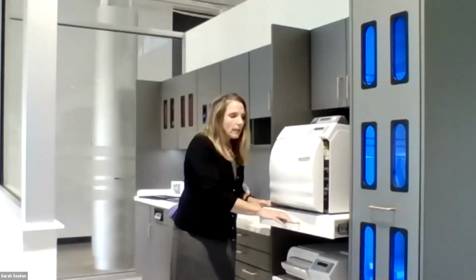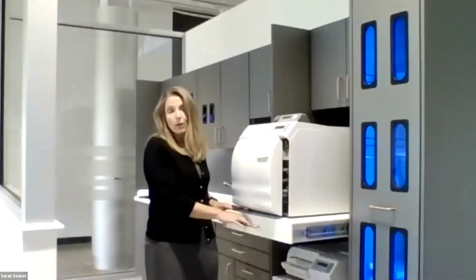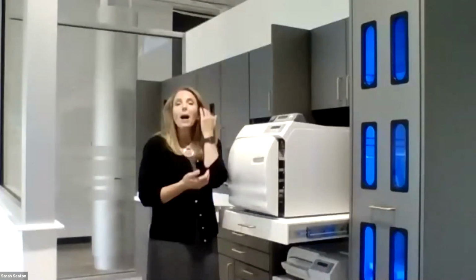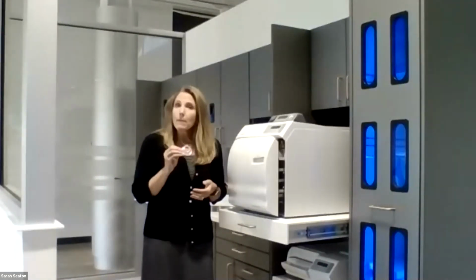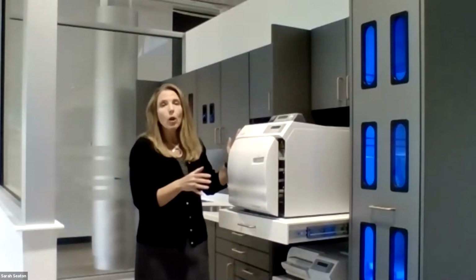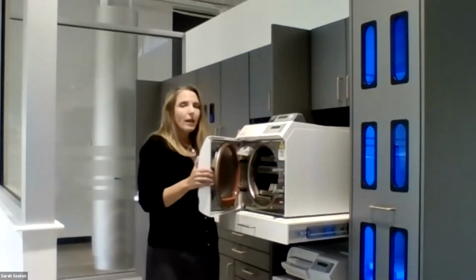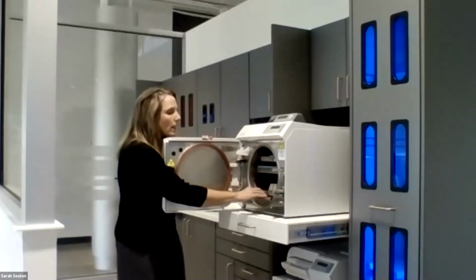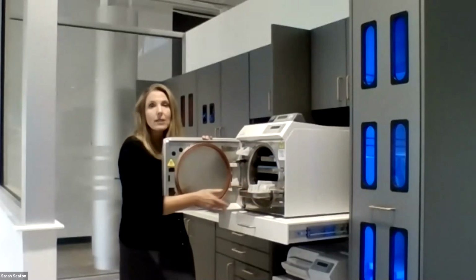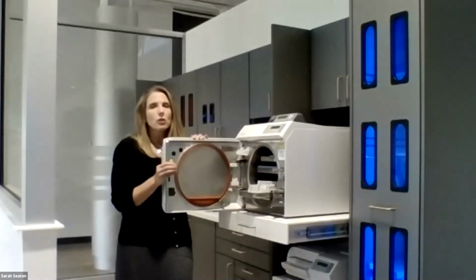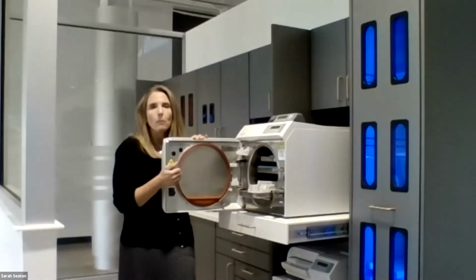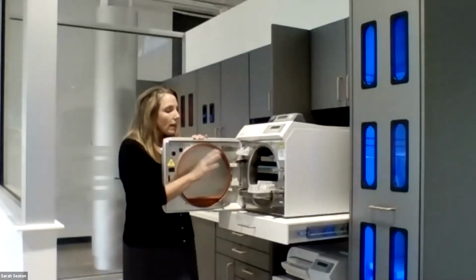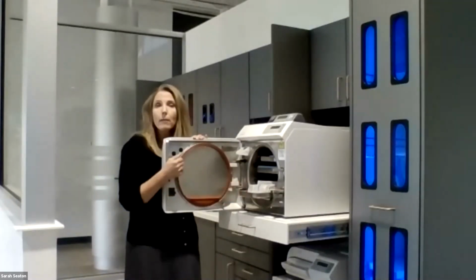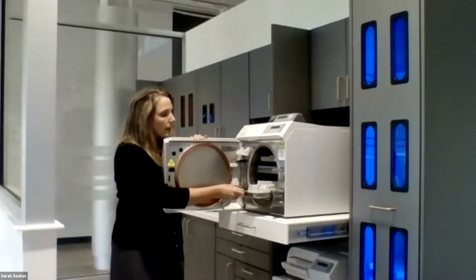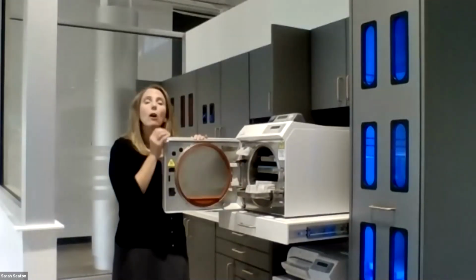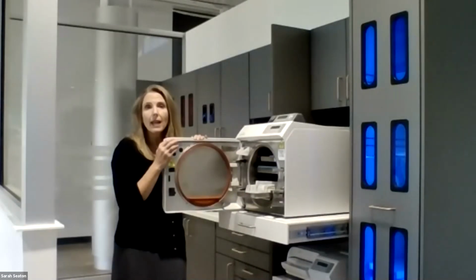Okay. With sterilizing, steam sterilizers, obviously what Midmark sells, happen to be one of the most popular methods for sterilization. Some of the keys to sterilization is proper loading of the sterilizer. So you want to make sure that you leave enough room for free flow of the steam and heat to reach all those instruments. You want to make sure that you're not overloading and jamming in too many instruments at the last minute. Okay. If you're using pouches, the CDC recommends that pouches be on edge, as I've got here, with our pouch rack. Midmark, with all of our new units, provides a pouch rack to facilitate that loading.